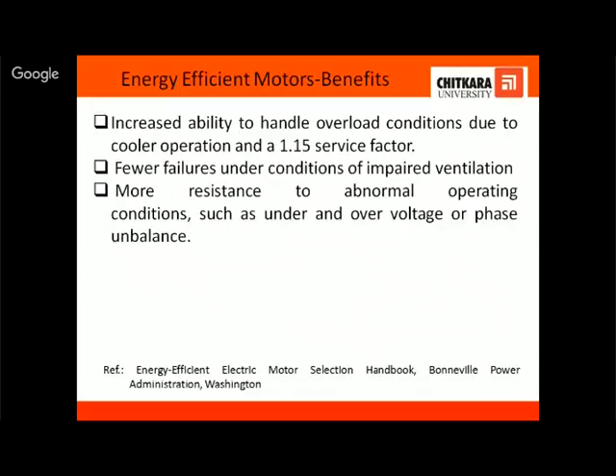Then there are fewer failures due to impaired ventilation. That is, if ventilation is not adequate, the temperature rise is basically low. So there are fewer chances of failures, and they are more resistant to abnormal operating conditions such as under voltage, over voltage, or phase unbalance, etc. So these are more benefits of the energy efficient motors.